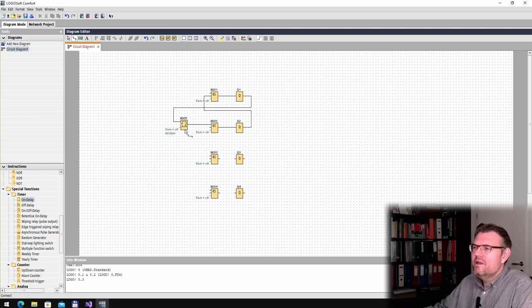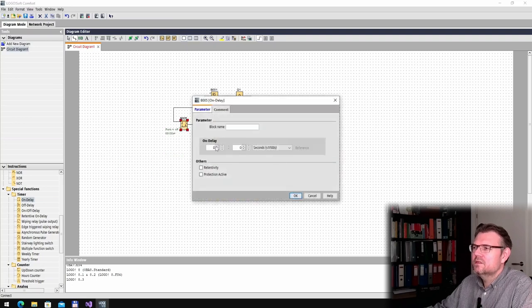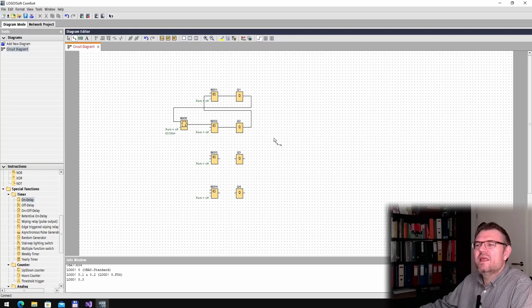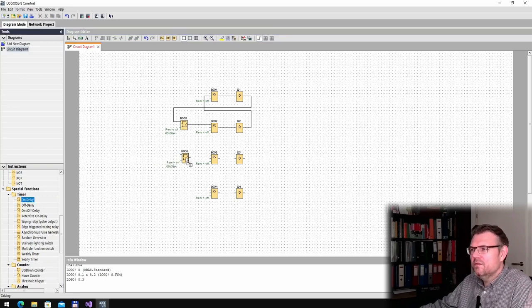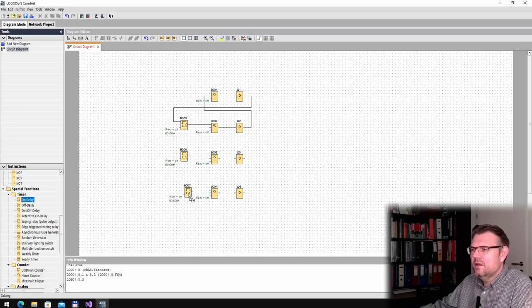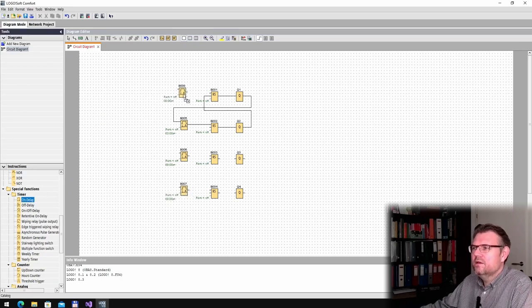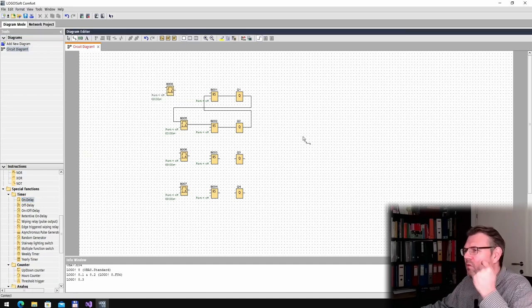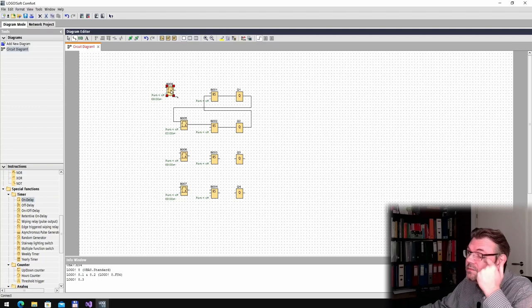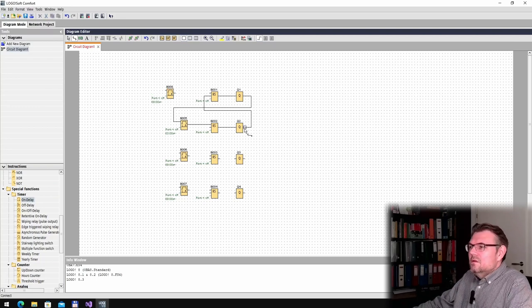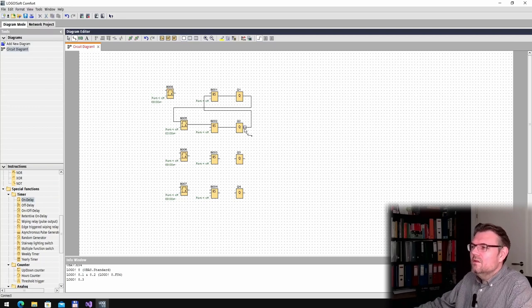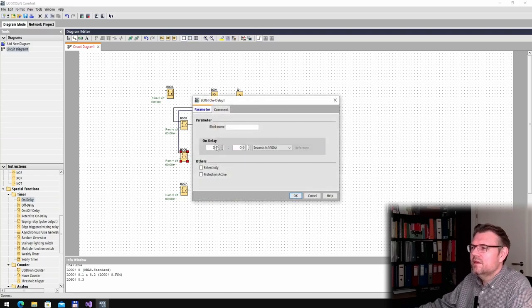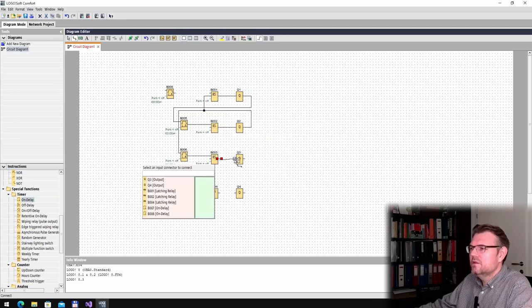Here we can adjust. I will use three seconds. Every three seconds the next output will be on. So I will use here an on-delay. I have to do a little bit more to adjust this. So this output, an on-delay, three seconds, turn on this latch. This latch turns on that output.